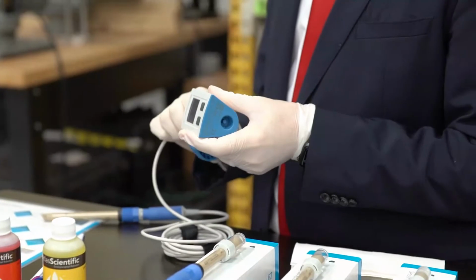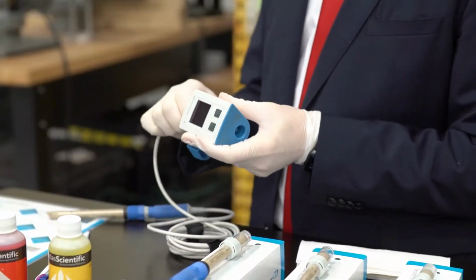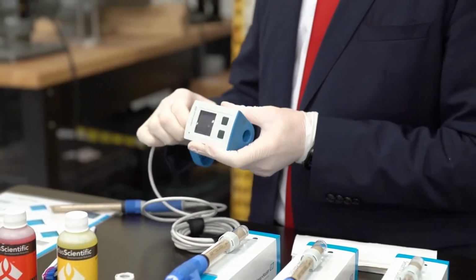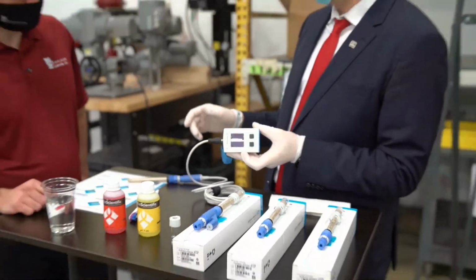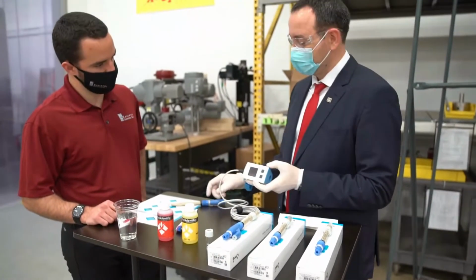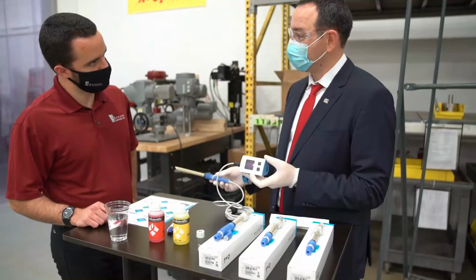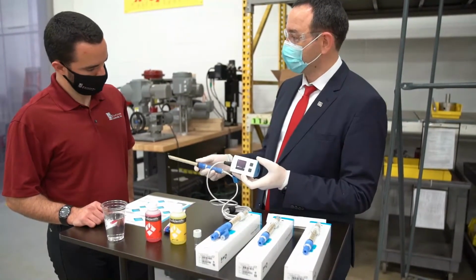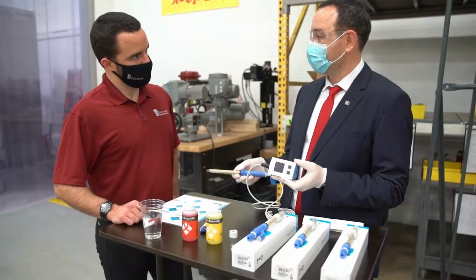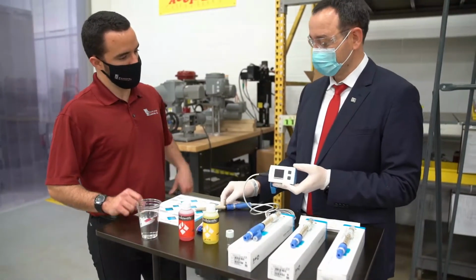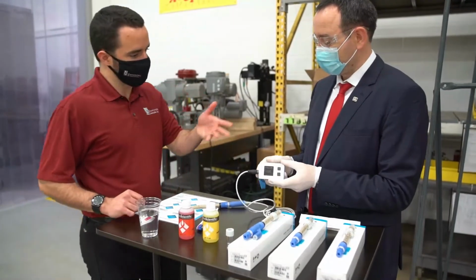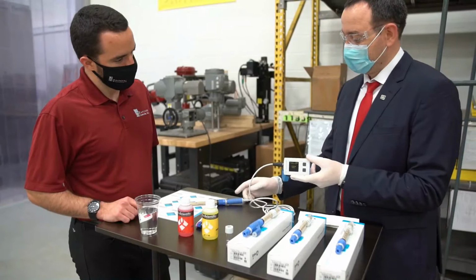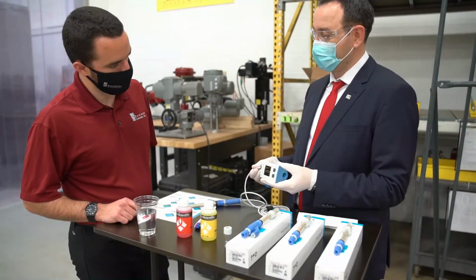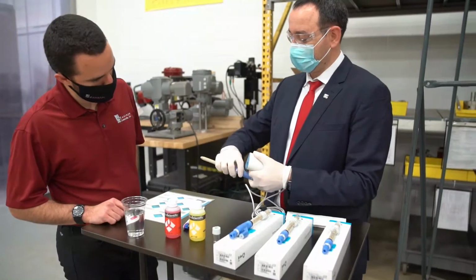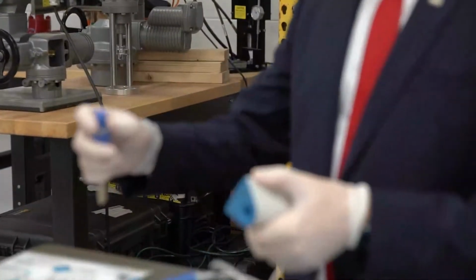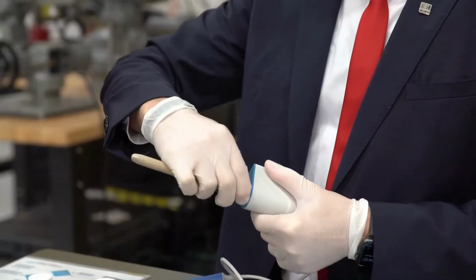So this battery operated portable device is very new and we use it for recalibrations or grabbing samples in the field. So it has multiple uses. In this case, I will show you how to use it for recalibration because the probe stores the calibration data and we can keep it on the shelf to be swapped in the field. Okay, and it looks like that's an M12 plug? Does it also have the MemoSense connection? Yes. So we can either connect it with the M12 cable connection or we can directly connect it to the probe here with the MemoSense connection.